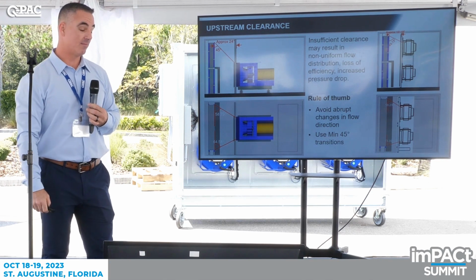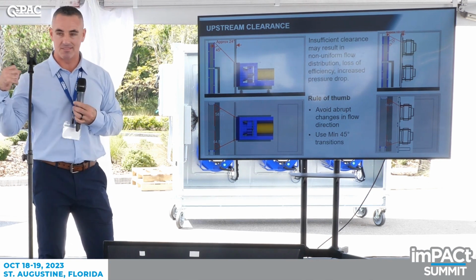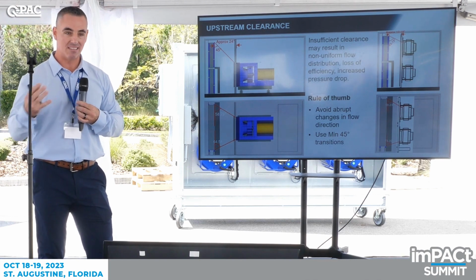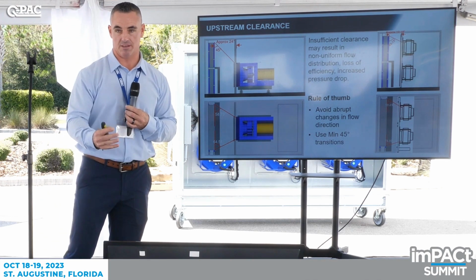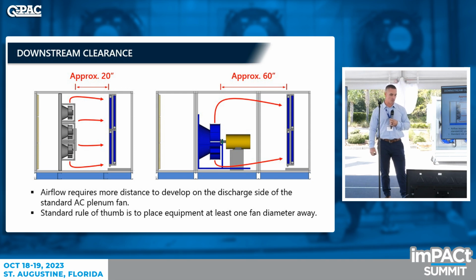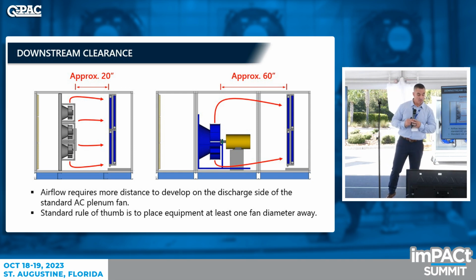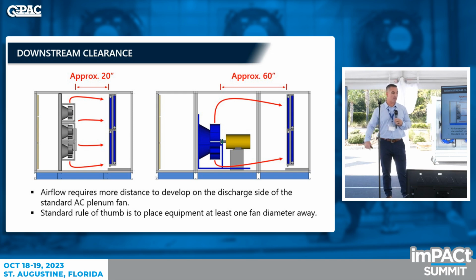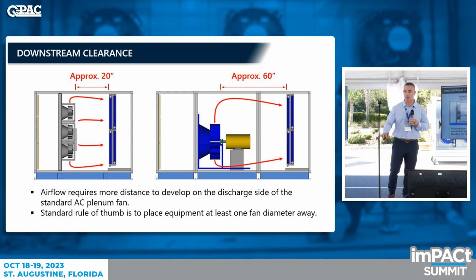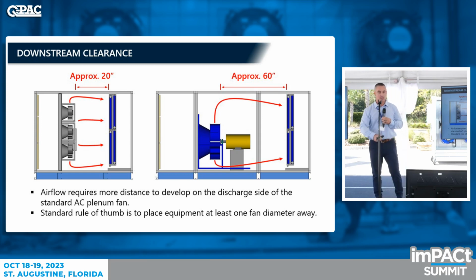Then you go to a fan wall, and truth be told, it's not just Q-PAC. If you go with multiple fans in an airstream, you can get closer to a coil. Downstream, a typical rule of thumb is approximately 2 to 3 fan diameters. I took this slide from Q-PAC, which says at least 1 fan diameter, but I'd say 2 to 3 before you're blowing through a coil or filter or something like that. You can get much closer with multiple fans. The idea is you don't want to get too close, because you need to access that fan. So accessibility is really going to drive that distance.